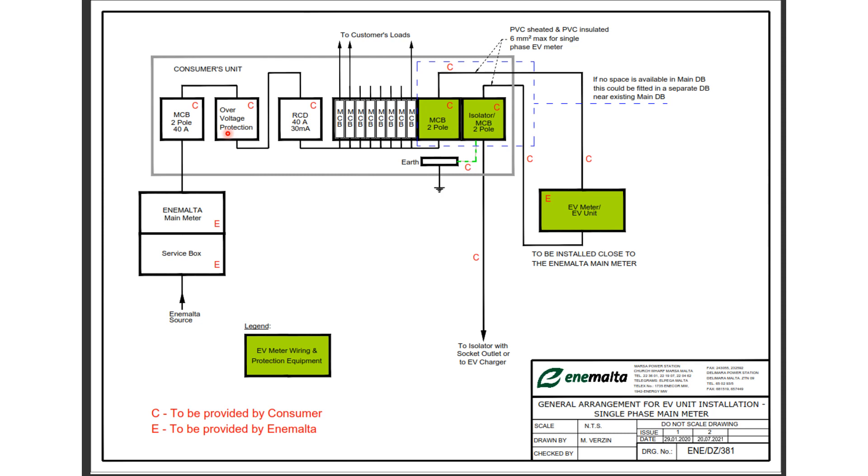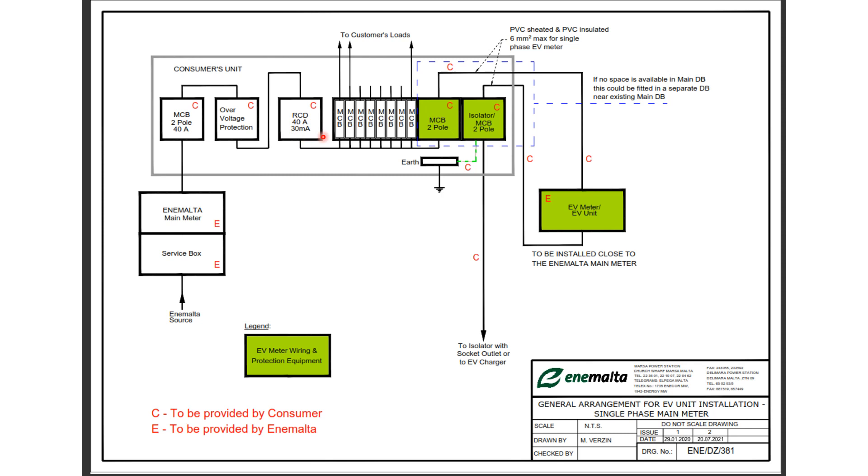Now after the overvoltage we will have the RCD 40, 40 amps current and 30 milliamps. Now if you have an apartment you may find the RCD in the common space which may be 100 milliamps, and then you have another one protecting the apartment of 30 milliamps.